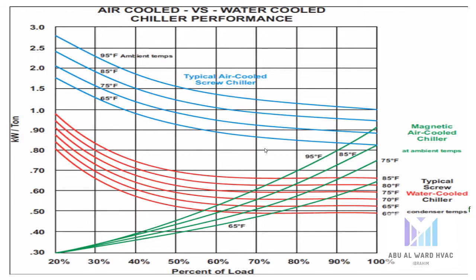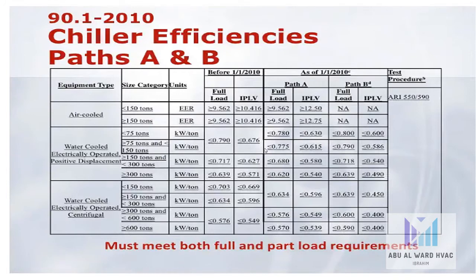Here these curves show the comparison between air-cooled vs water-cooled chillers performance. You can see that the water-cooled are more energy efficient compared to the air-cooled chillers for the same capacity and the same temperature ranges. We have another type, magnetic air-cooled chiller. It is in between.